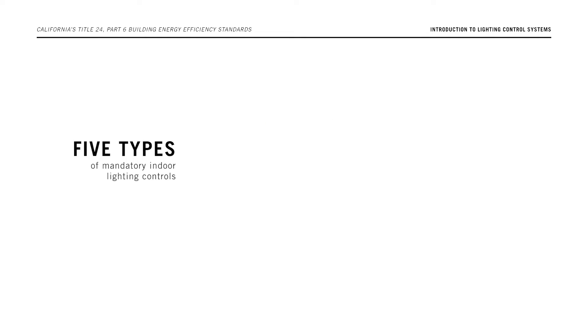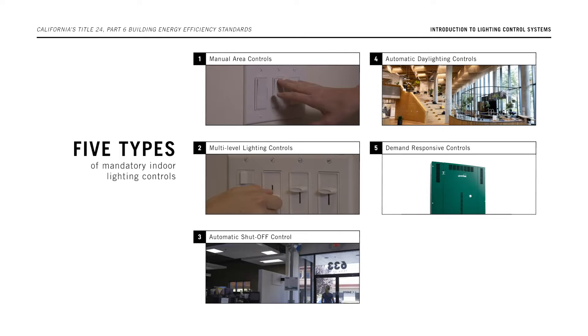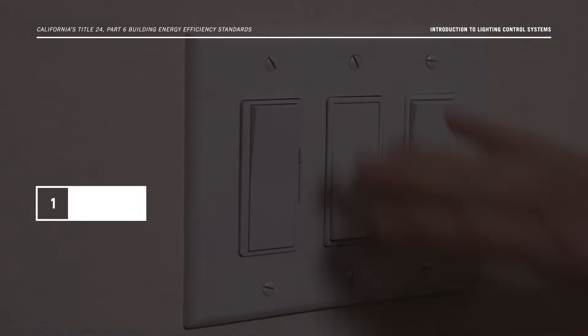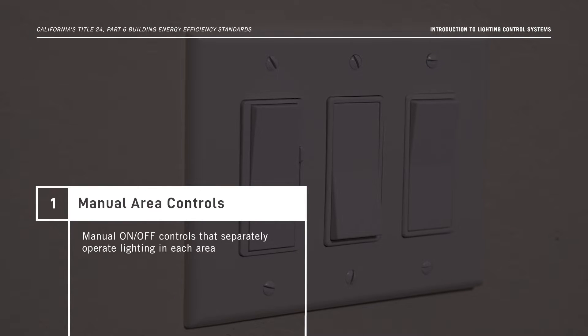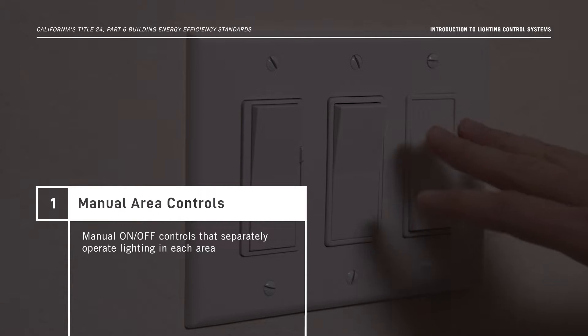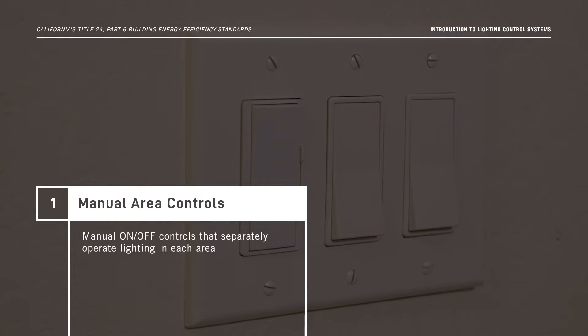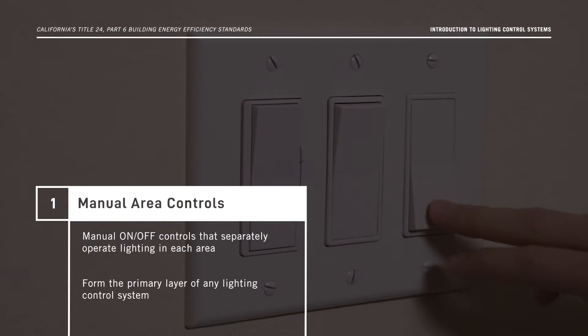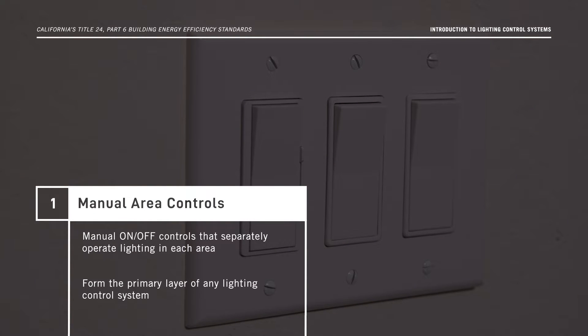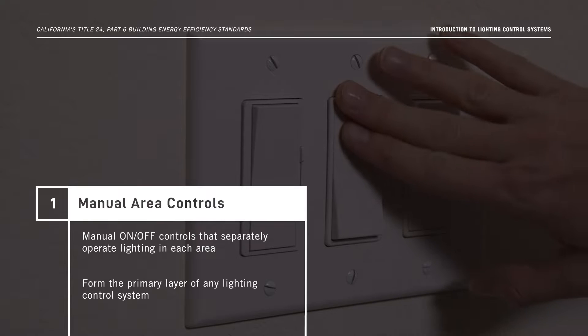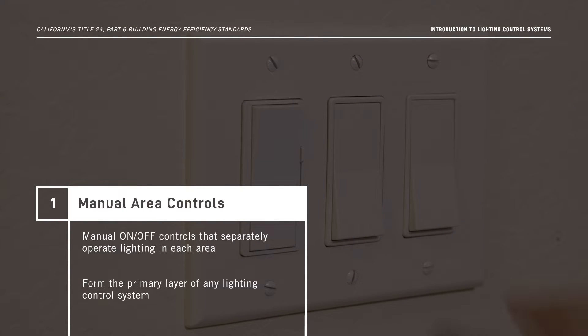Now we'll tell you about the five types of mandatory indoor lighting controls and review the control interactions required under the Energy Code in Section 130.1. Starting with manual area controls — they're manual on-off controls that separately operate lighting in each area. An area is any space with ceiling height partitions or walls. These controls form the primary layer of any lighting control system and have been required under the Energy Code since its inception in 1978.